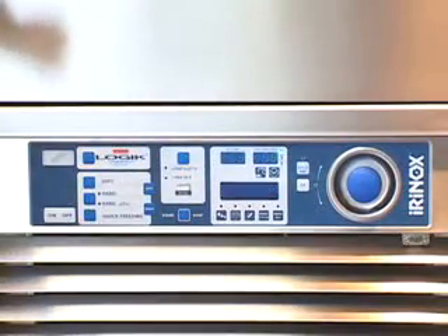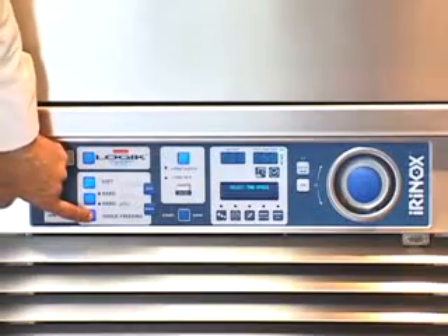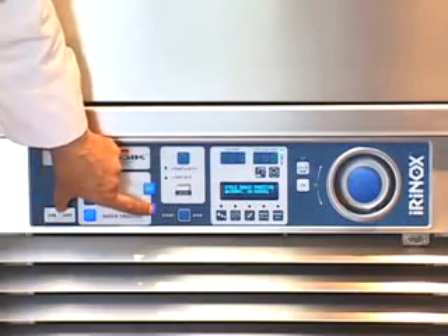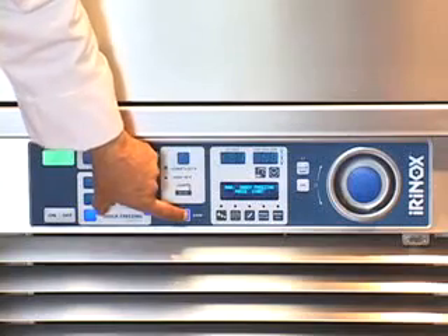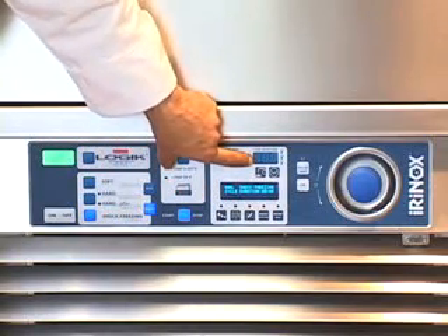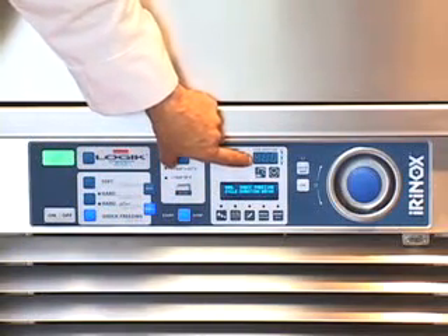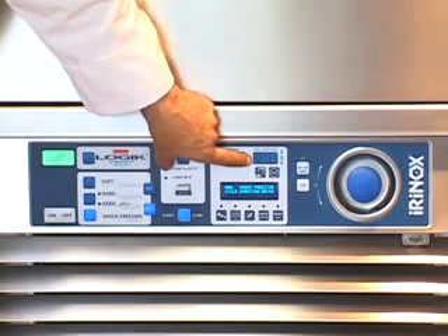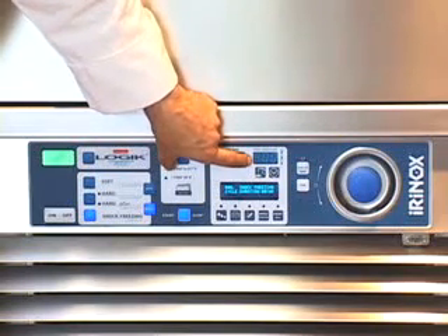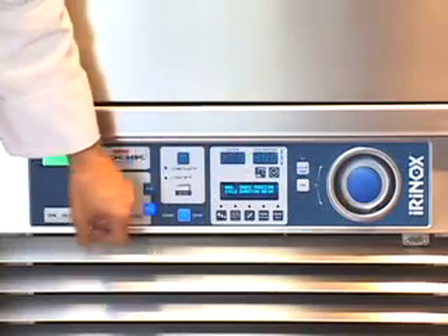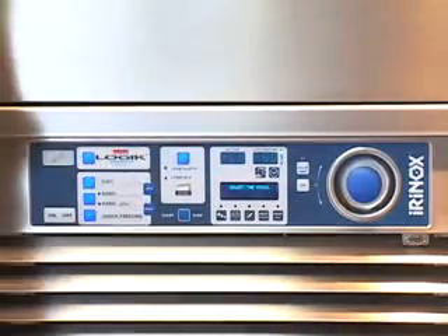I will now demonstrate the shock freeze manual mode. Again, I select the shock freeze cycle, and when I select the manual and hit the start button, the timer will automatically read 4 hours. It'll run between -30 and -40 degrees Fahrenheit for 4 hours, and then go into a hold mode where the unit will run approximately at 0 degrees Fahrenheit until I manually stop the unit.